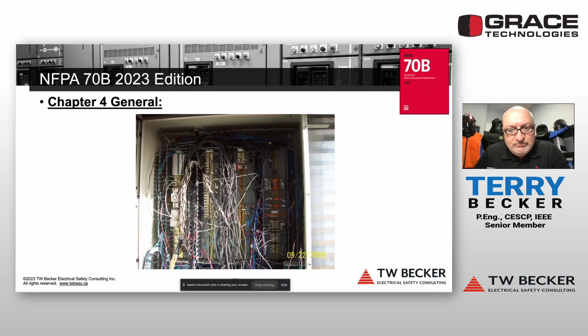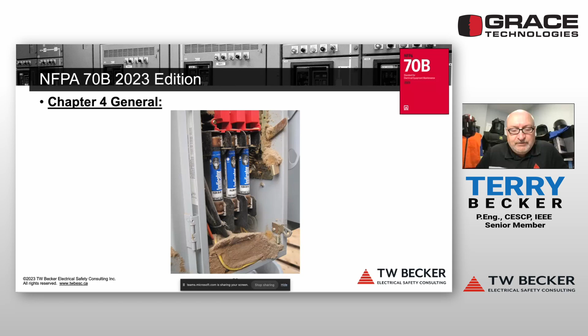That should be clean, the panduit should be covered. This is what you find when you inspect, and the outcome is resolving that we need to do some maintenance. That's a breaker that needs a lot of maintenance—I think that was a mining application. Even the stabs on an MCC starter bucket, you can see dust and dirt accumulating. That's an interesting picture, that one—and rodent nests.